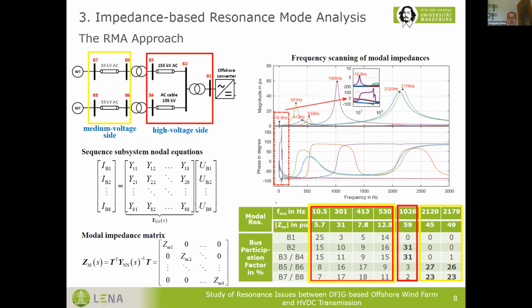The results to this case are presented in this table. As observed, for the resonance modes up to several hundred Hz, all the buses have more or less contributions to these resonances. While for the resonances above 1000 Hz, either the buses in the high voltage side or the buses in the medium voltage side are the resonance sources.